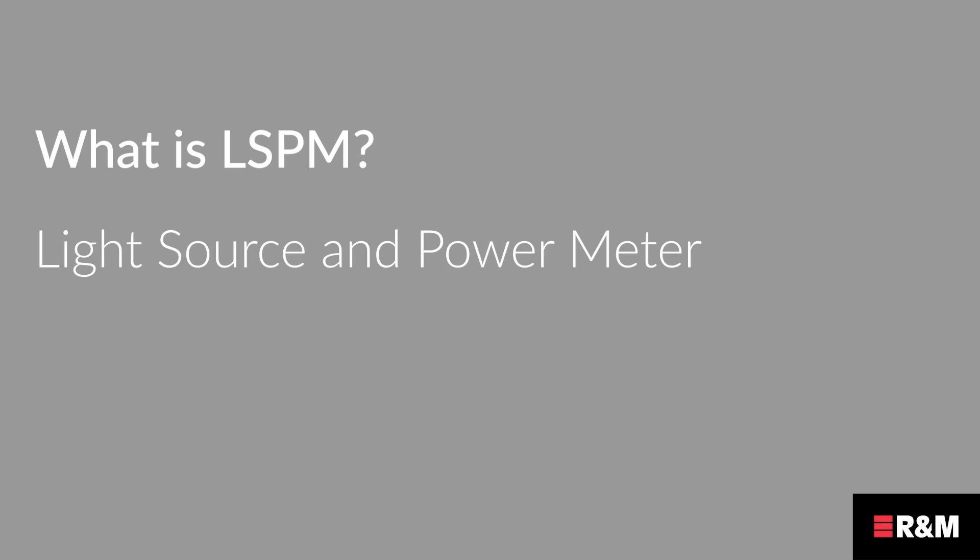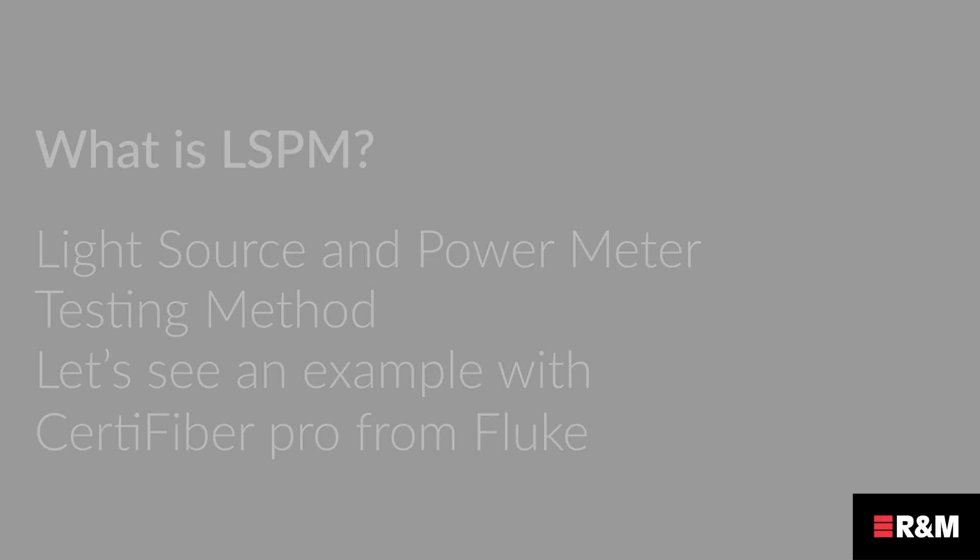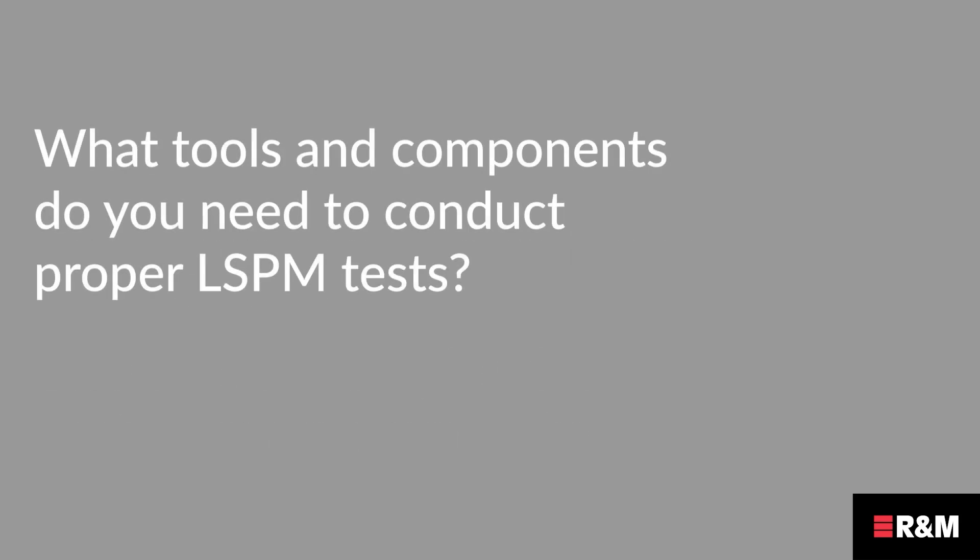LSPM or light source power meter is a testing method to test and certify fiber optic links. In this video we will use the CertiFiber Pro tester from Fluke to demonstrate, but there are many other testers on the market that are suitable. LSPM is a testing method according to the standards to certify fiber optic links with the key focus to test against a fiber loss budget. It is a very fast and precise method for testing link loss.